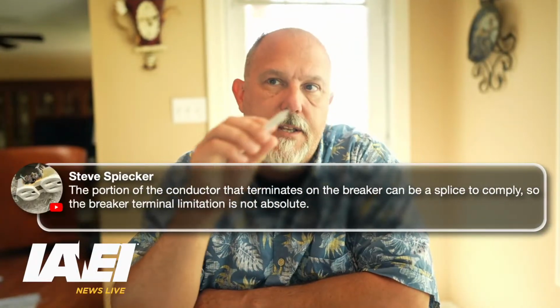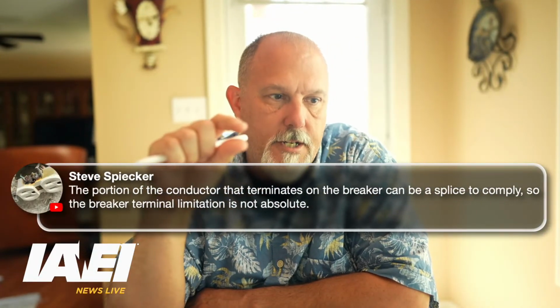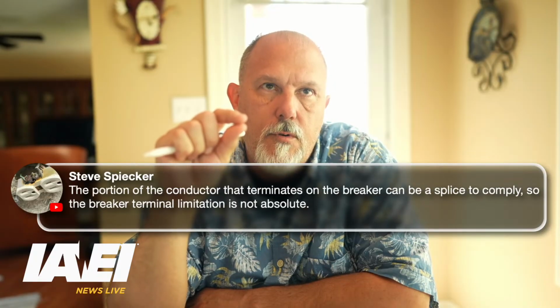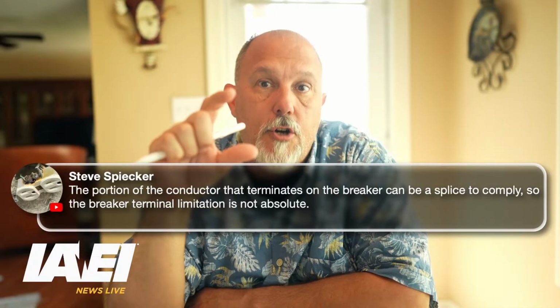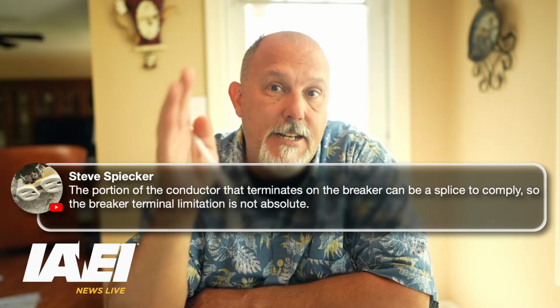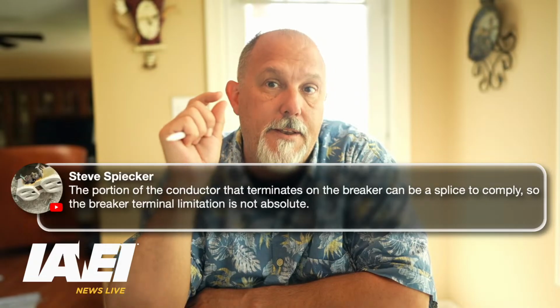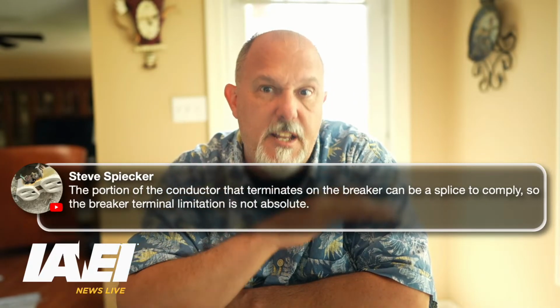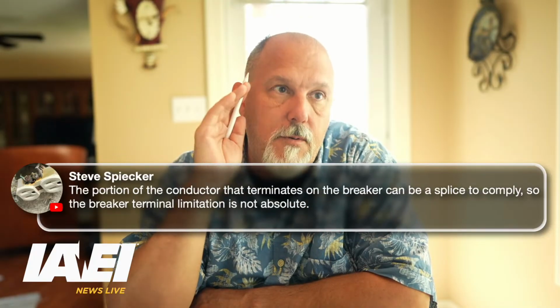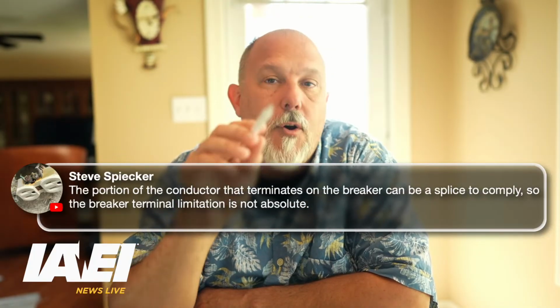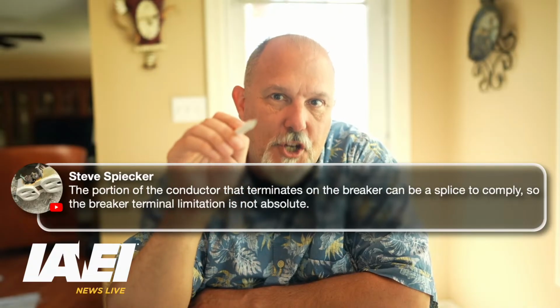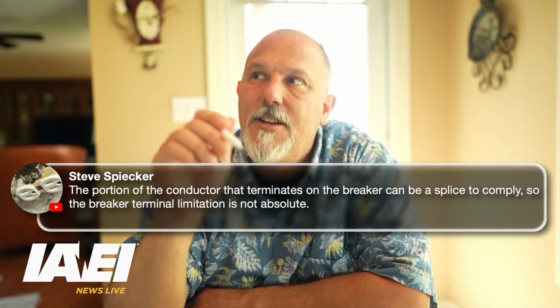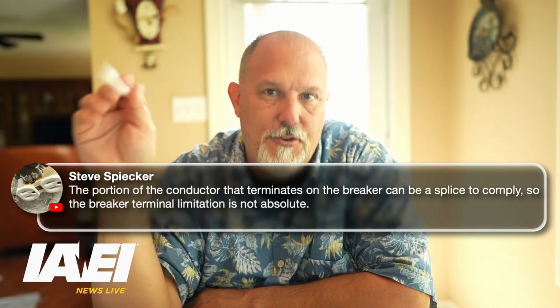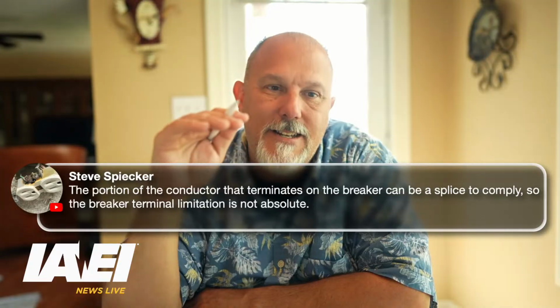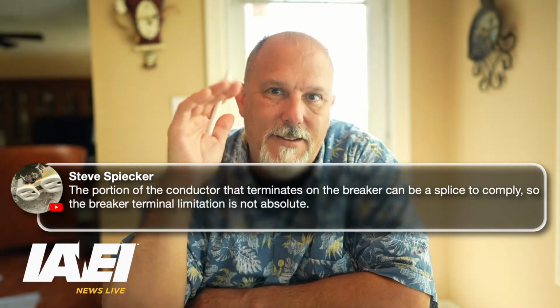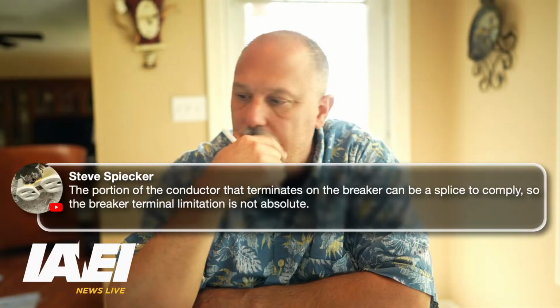But what you're talking about is coming off the breaker with a smaller conductor, or off with a larger conductor, going to a smaller conductor, and using it at its 90 degrees C ampacity, because you're no longer limited by the overcurrent device. I agree with you 100%. And honestly, you don't need a code permission to do that, but we added it in 210 and 215. You don't need a code permission for that, but we added it, so not a big deal.